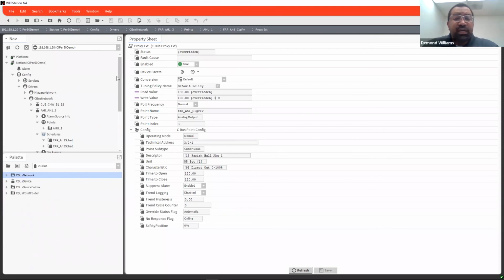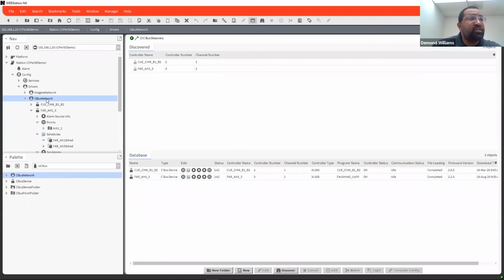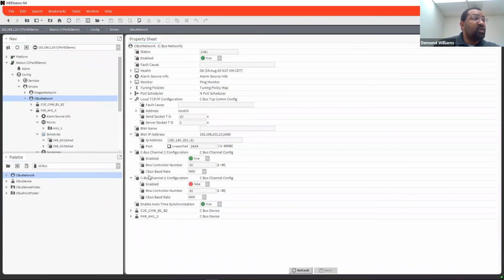One of the things also is that on the Clif controller itself, it does still have your two standard RS-485 network 1 and network 2. The Clif controller only utilizes RS-485 port 1. It does not utilize port 2. When you go into the configuration or even the CBus network here, it does talk about the second bus, but like I say, the second bus isn't actually used at this time, which is this channel here, which is actually disabled.